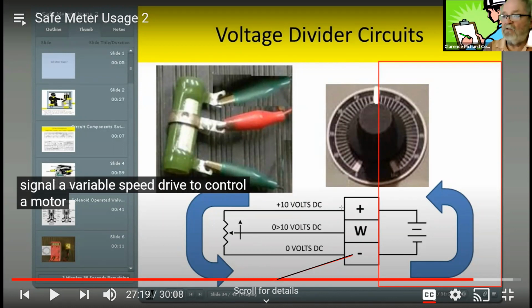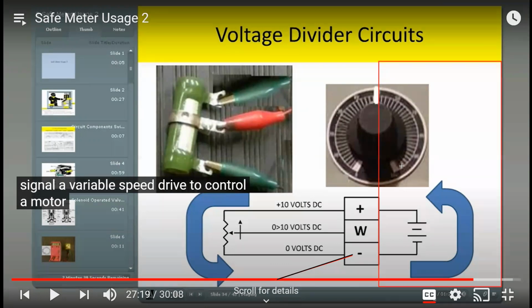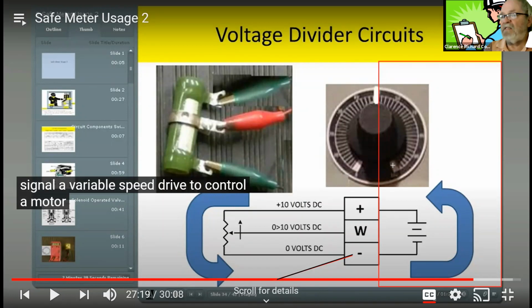We're just talking about the same circuit we had before with the pneumatic, the hydraulic. So if I turn this all the way up to 10, I'm expecting this up to 100. I'm expecting this to go full speed, but it's not. I clipped one of my leads. I put my meter on DC. I set my manual range to 20, because that's over 10 volts. And then I'm going to take my other red lead. I'm going to do some checking around to see what's going on here.